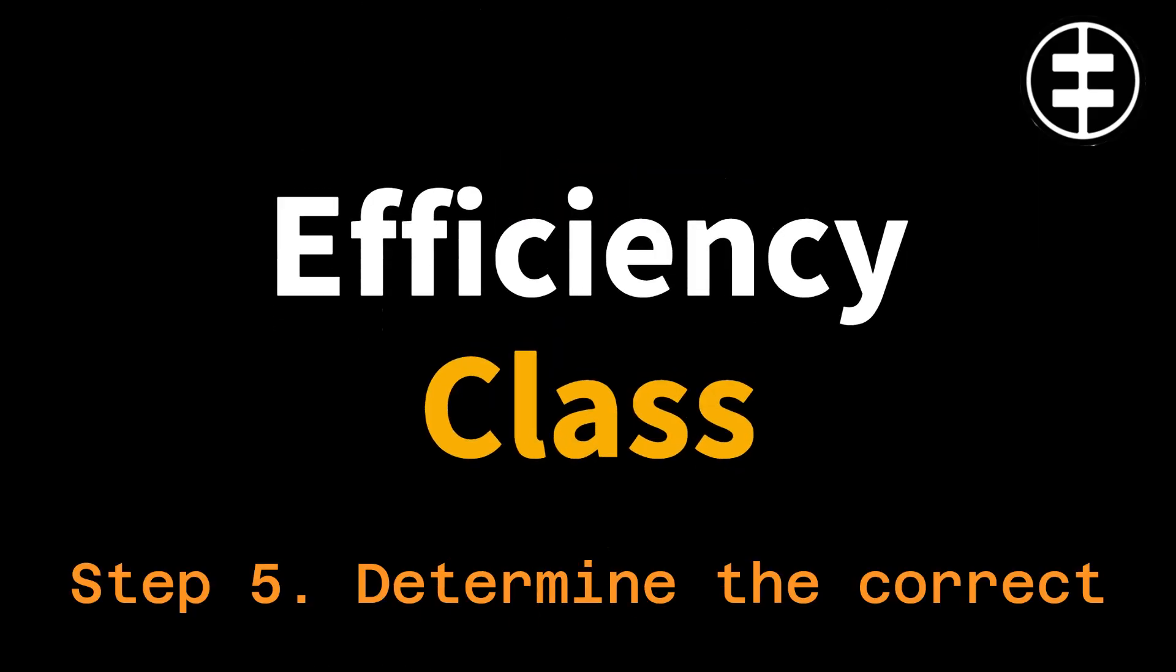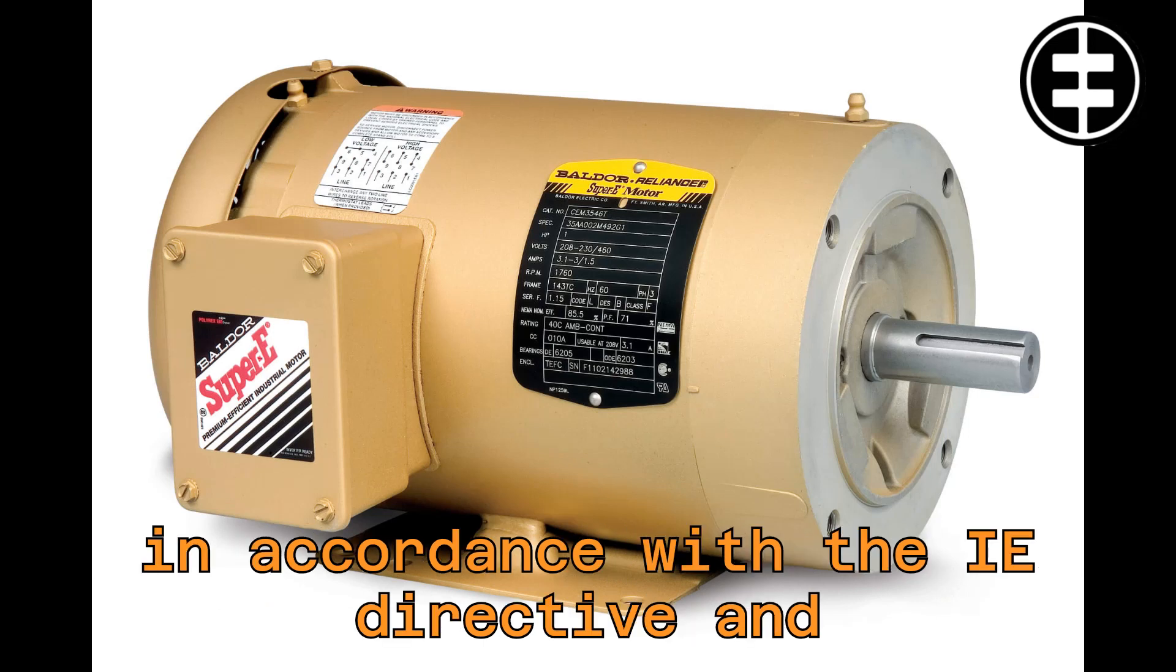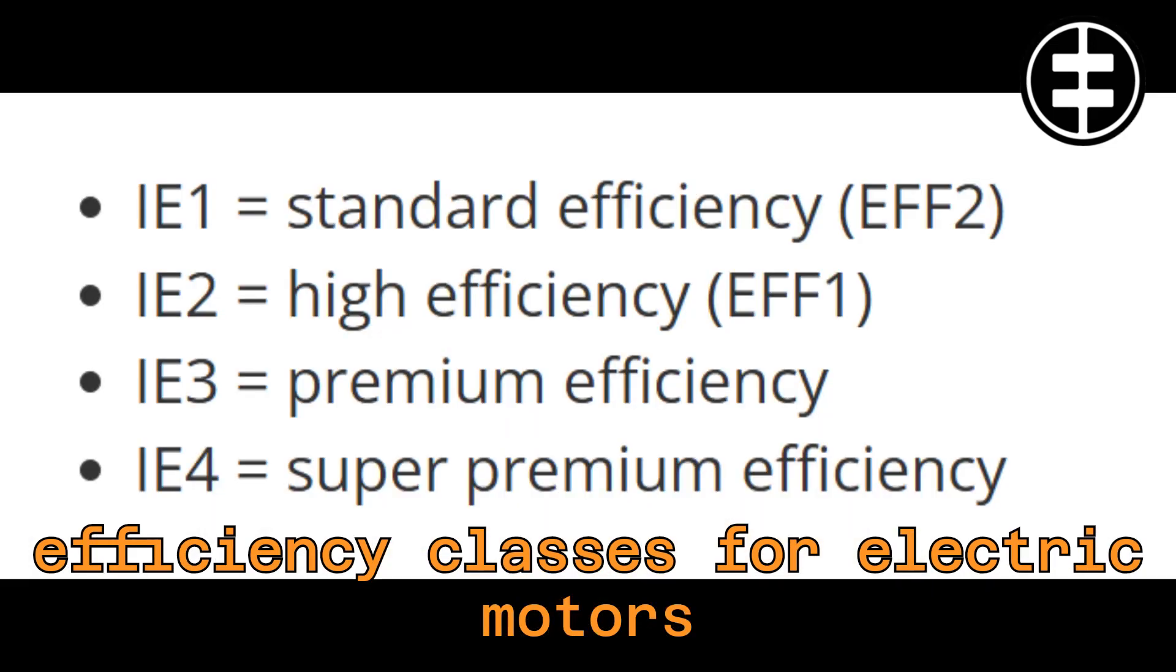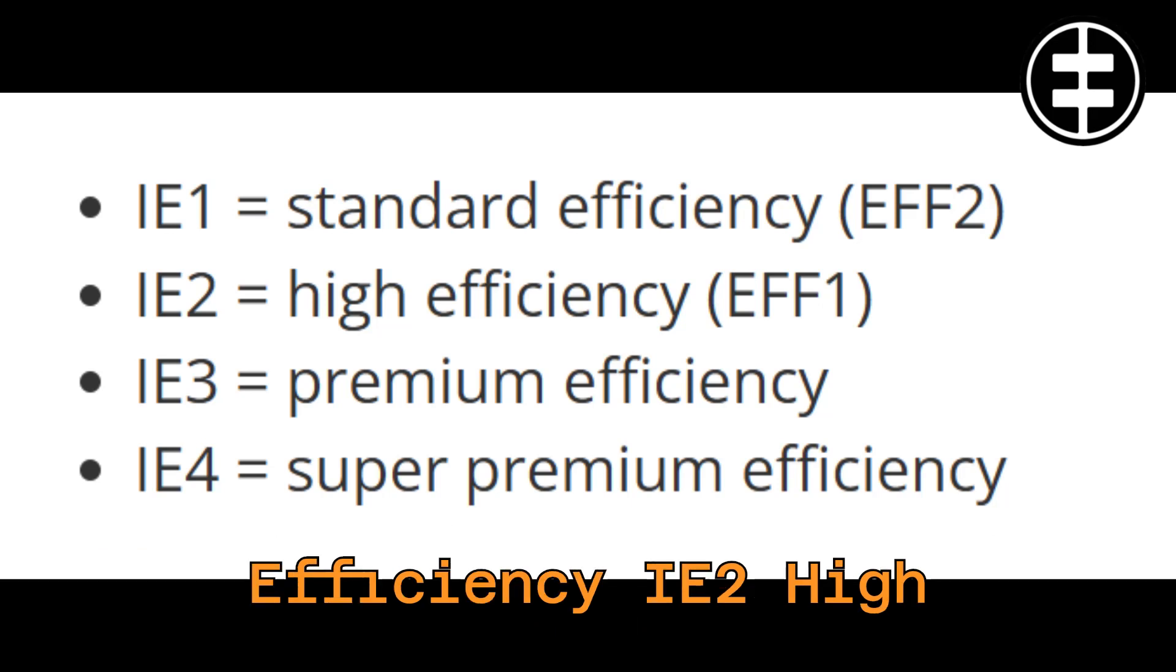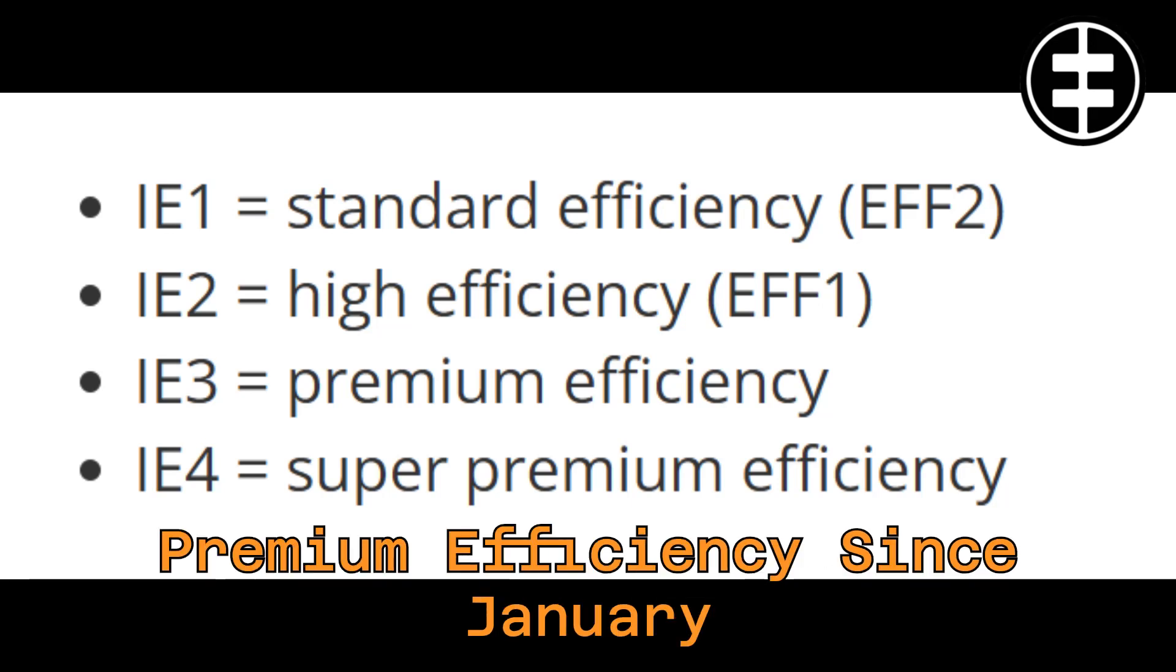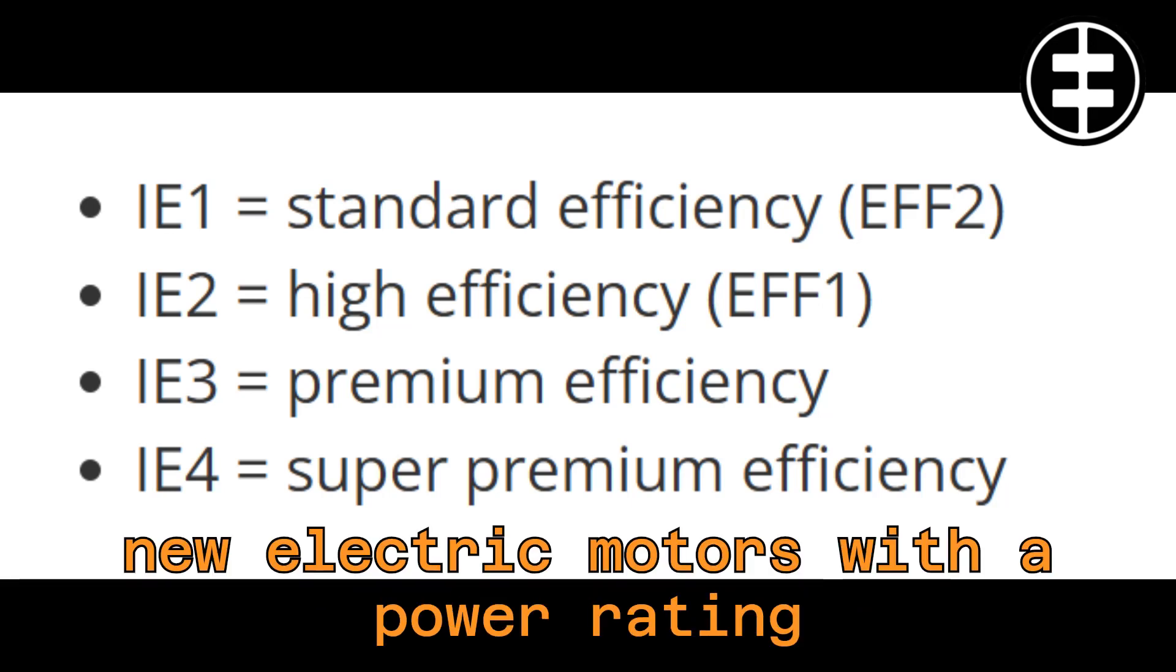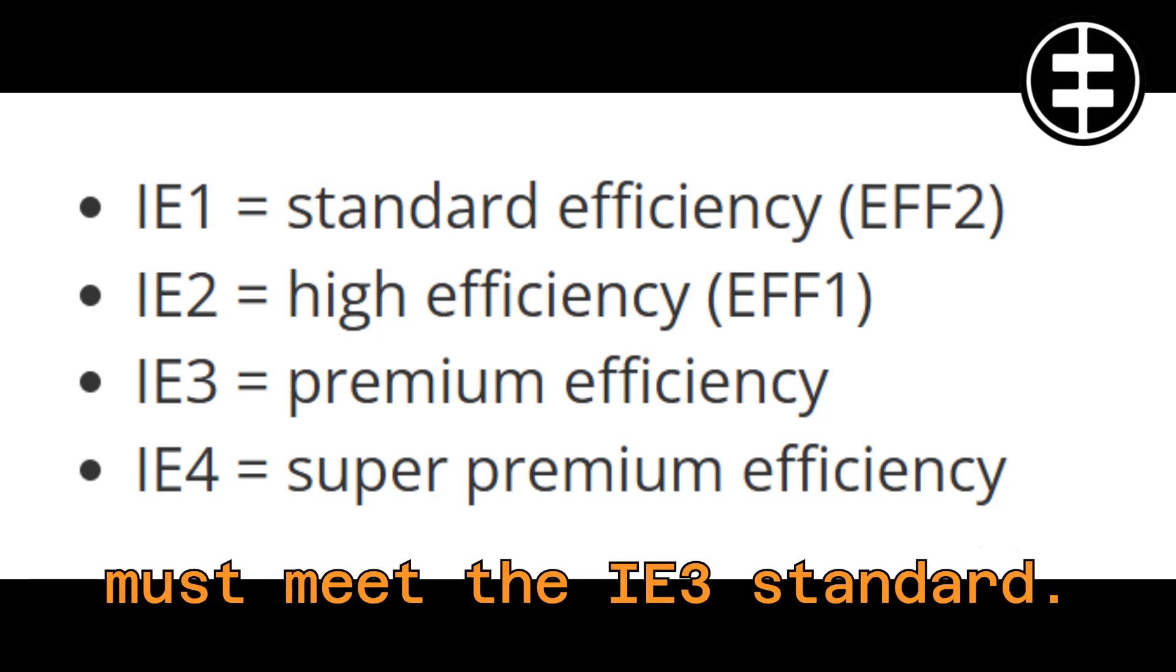Step 5. Determine the correct efficiency class. From June 16, 2011, most motors on the market must be marked in accordance with the IE directive and classified with an efficiency class. The efficiency classes for electric motors are IE1 Standard Efficiency, IE2 High Efficiency, IE3 Premium Efficiency, IE4 Super Premium Efficiency. Since January 1, 2017, all new electric motors with a power rating of 0.75 kW or above must meet the IE3 standard.